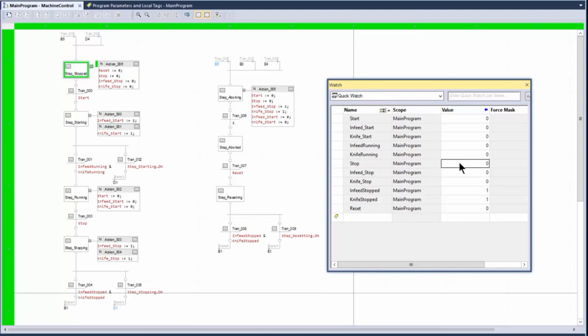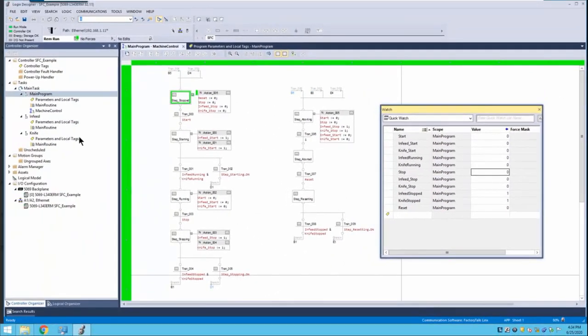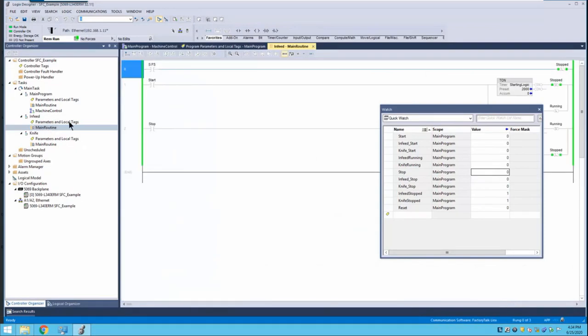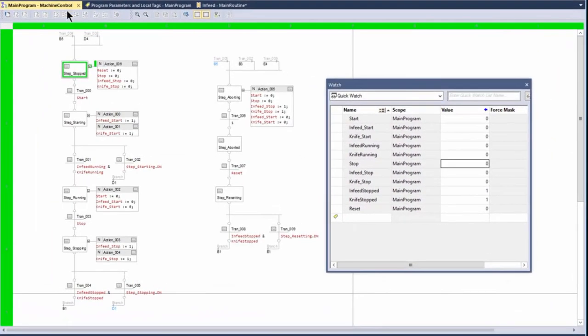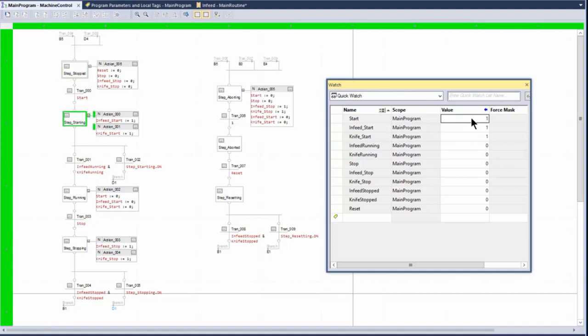Let's increase one of the timers in the section logic to test our aborting sequence. Commanding a start, we see that only one of the sections reports back as started in time, so the sequence transitions to the aborting step and the sections are commanded to stop.